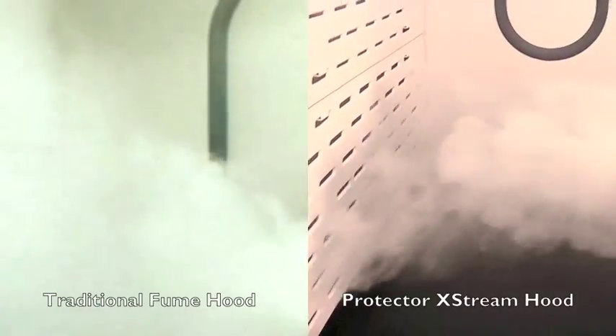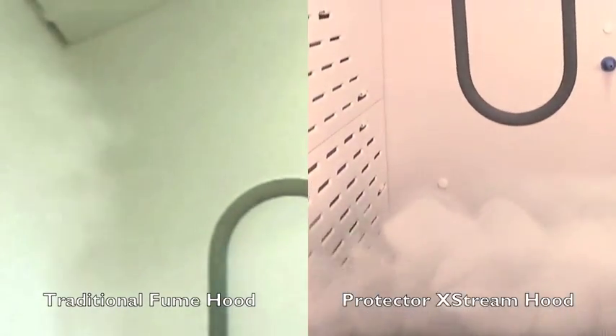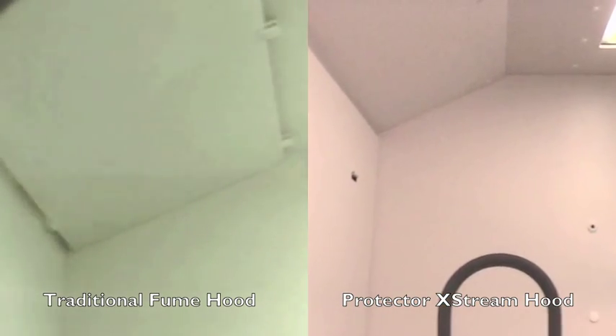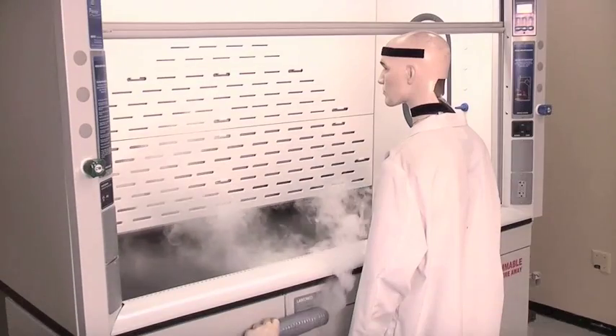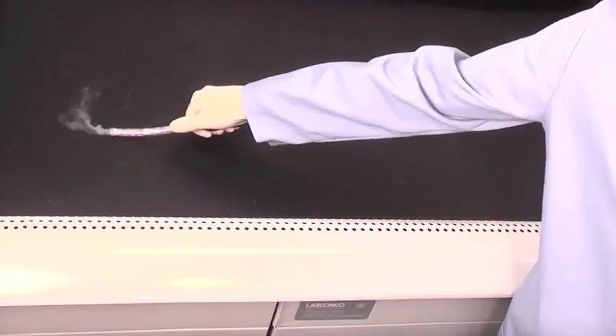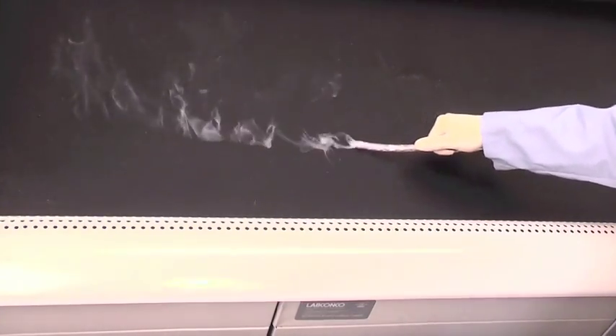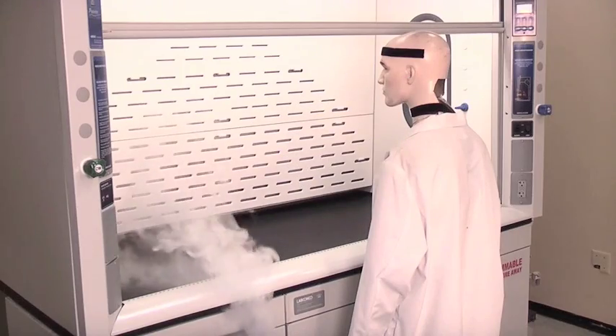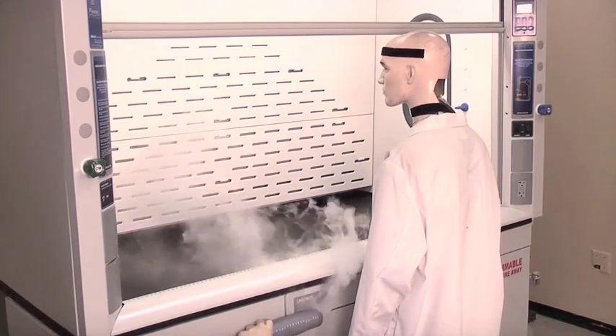The result is a dramatic reduction in the concentration of hazards within the fume hood. This efficient airflow is created by several unique features of the Protector XStream. The aerodynamic curve of the airfoil, along with the large radial edge of the work surface, function together to correct airflow prone to reversal in traditional fume hoods, directing air to sweep the dished work surface for maximum containment.